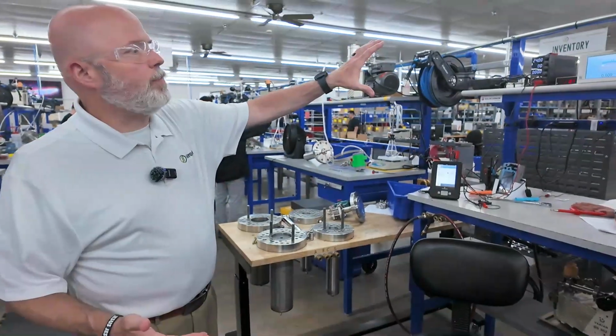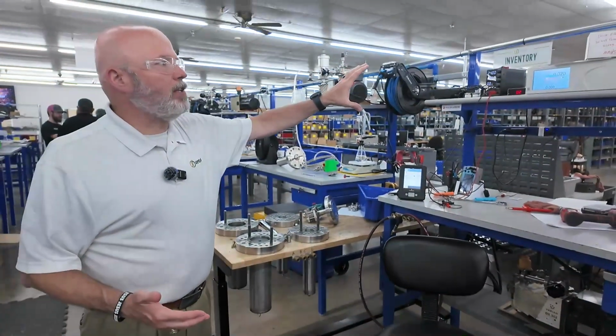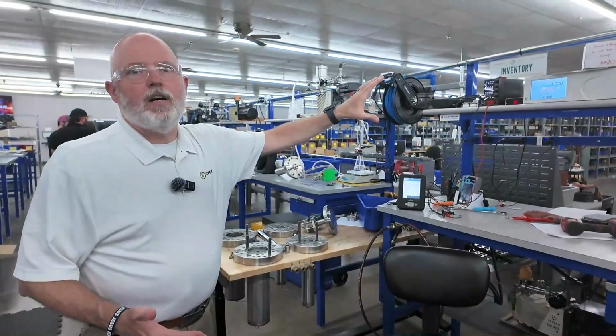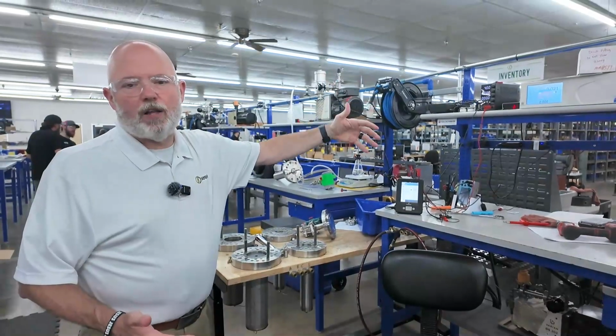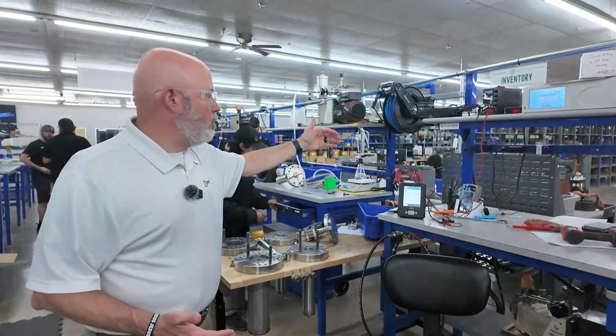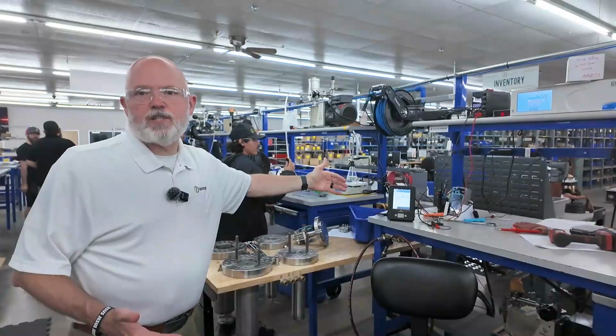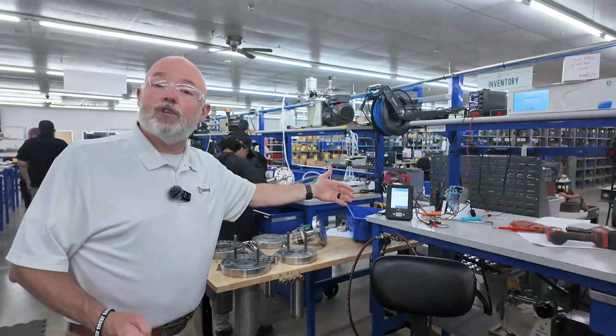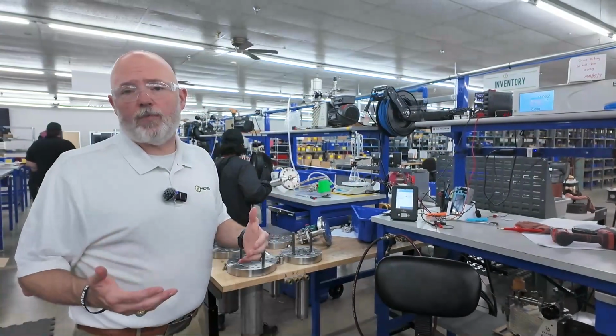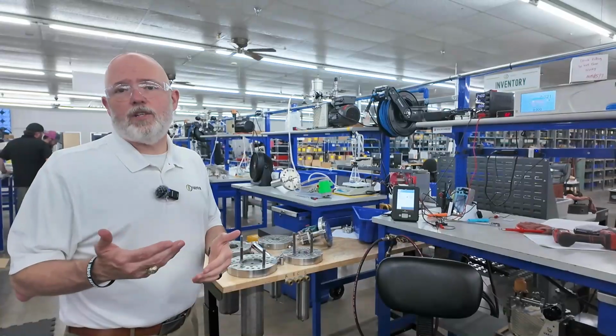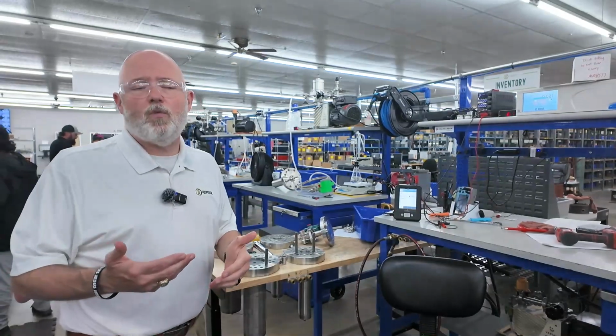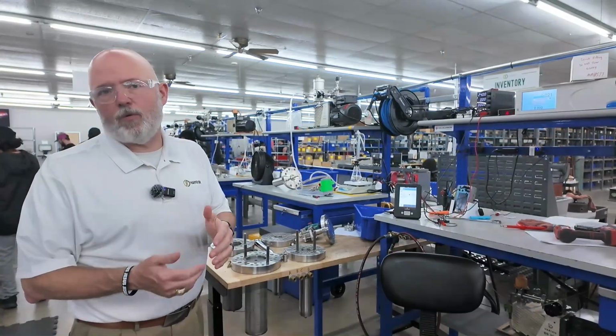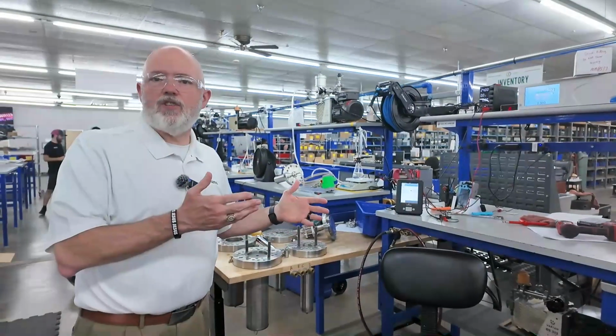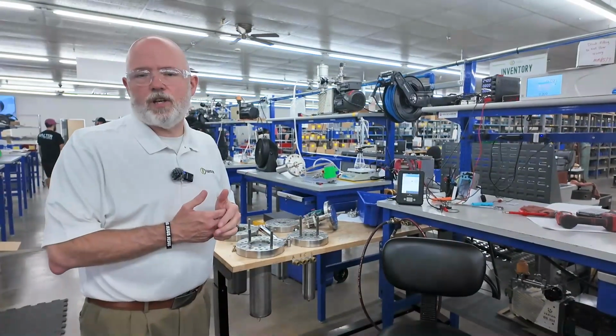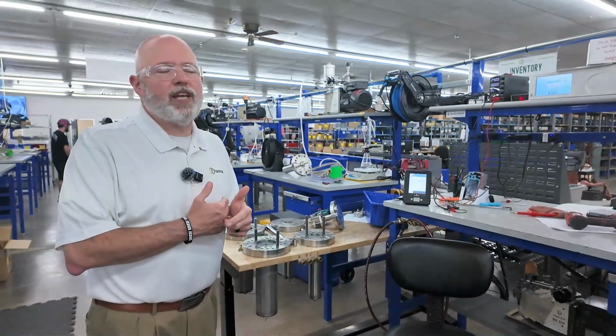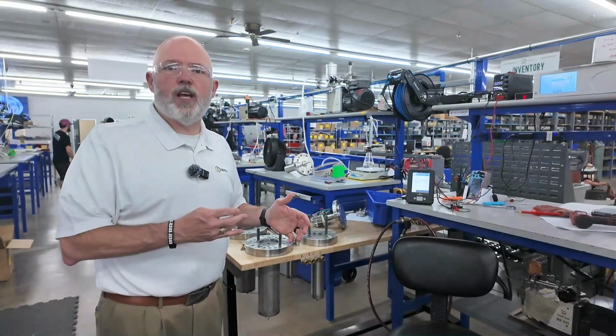Our controllers up here will automatically track the 5 points of calibration, and then we typically use a Trex communicator to communicate with the transmitter. So if the customer requires any custom ranges different from what's set from the factory, we're able to change those settings and calibrate the new settings.